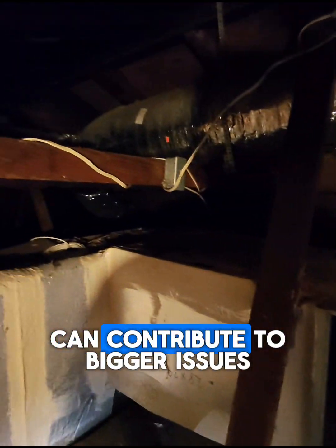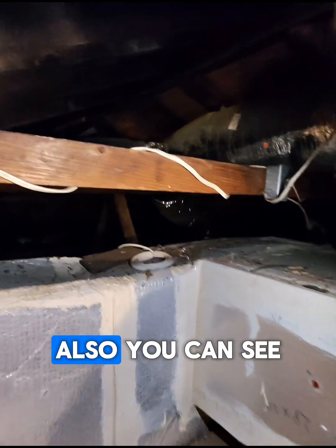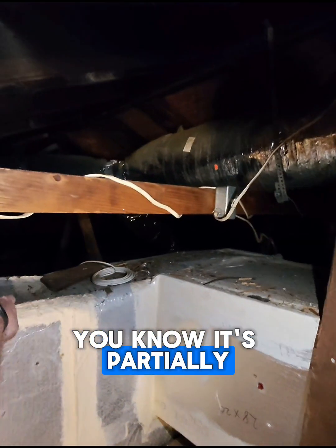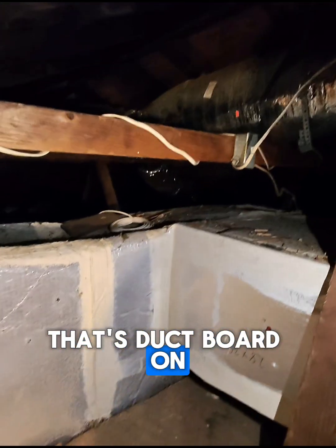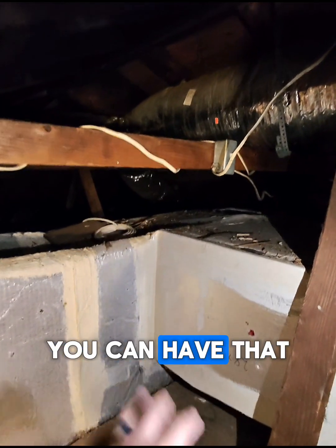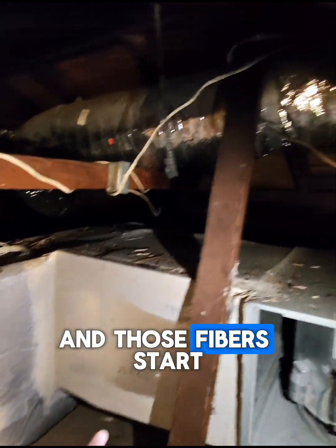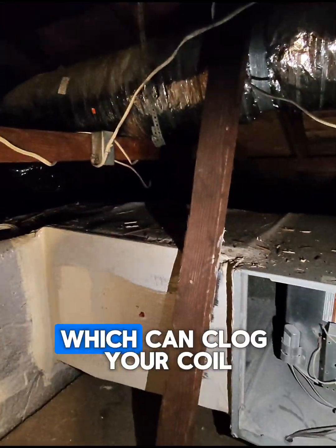So all these little things add up and can contribute to bigger issues. Also, you can see the return is partially collapsed right there. That's ductboard on the inside. Whenever that collapses like that, you can have that ductboard start coming apart, and those fibers start releasing more into your airstream, which can clog your coil.